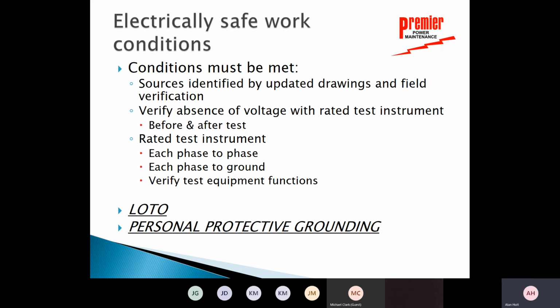Okay. In addition, verify absence of voltage with a rated test instrument before and after. We've talked about that every year in our electrical safety training: when you're using a meter to test for voltage, of course, you've got your rubber gloves on unless you know it's less than 50 volts. You test the meter works first, then check for the equipment, and then go back and make sure that the meter still works. For rated test instruments, you test each phase to ground, you test each phase to phase, and then you verify that the test equipment functions after the end. So again, test before, phase to phase, phase to ground, and the test equipment, okay?